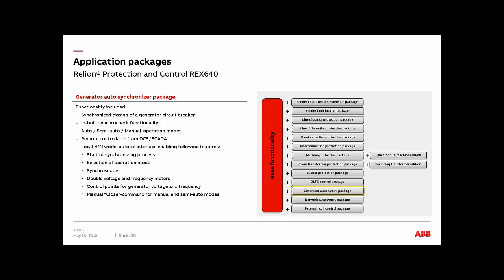And you're going to have control points for generator and voltage frequency. And through your HMI, you could also issue, of course, your manual close or open as well, if you are in one of these two modes where you choose to close yourself based on the synchroscope information.